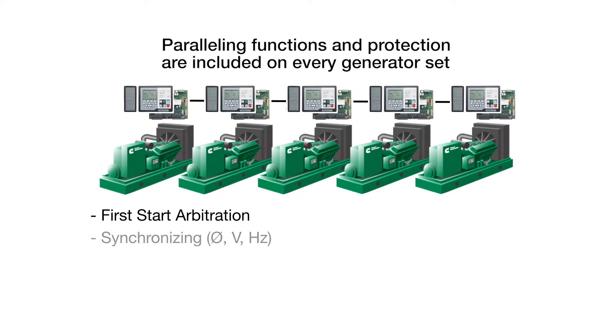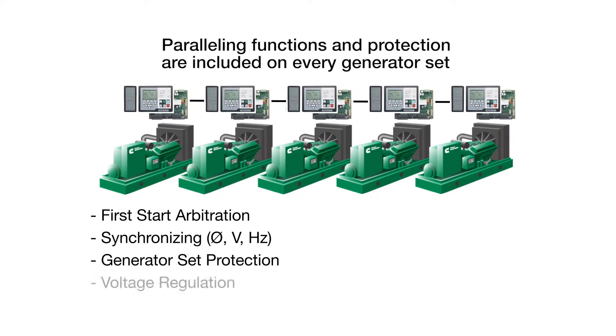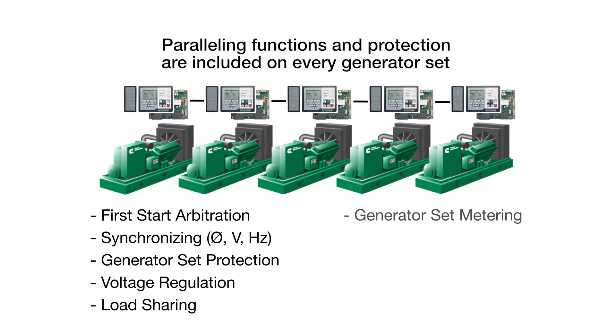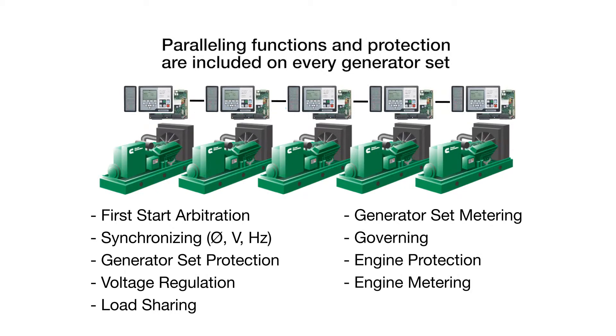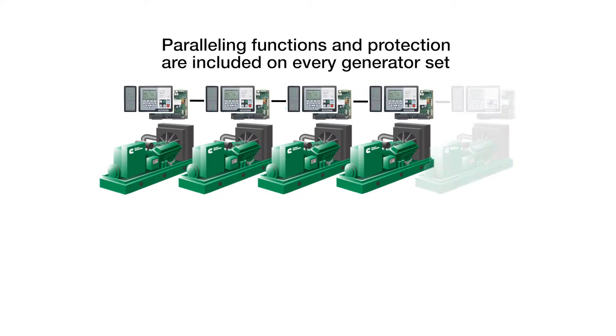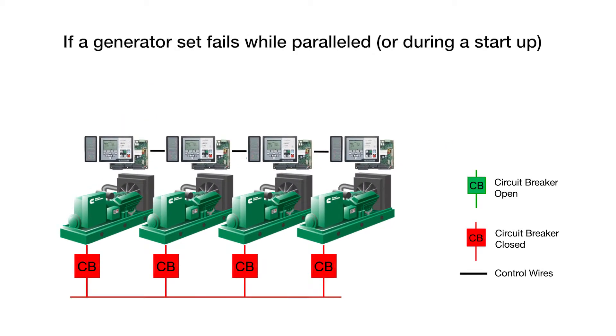In distributed logic architecture, the paralleling functions are included on each and every generator. Neither a paralleling master control nor switchgear control are needed to perform paralleling.